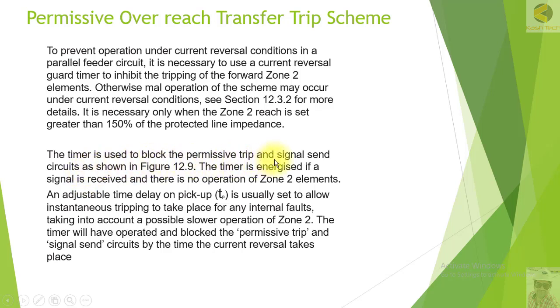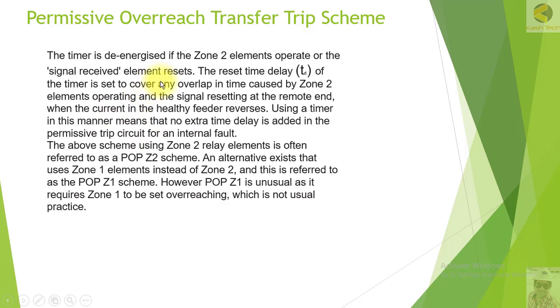The timer is used to block the permissive trip signal send circuits as shown in the figure. The timer is energized if a signal is received and there is no operation of the zone 2 element. An adjustable time delay on pickup is usually set to allow instantaneous tripping for any internal faults, taking into account a possible slower operation of zone 2. The timer will have operated and blocked the permissive trip and signal send circuits by the time the current reversal takes place, ensuring no extra time delay is added in the permissive trip circuit for an internal fault.